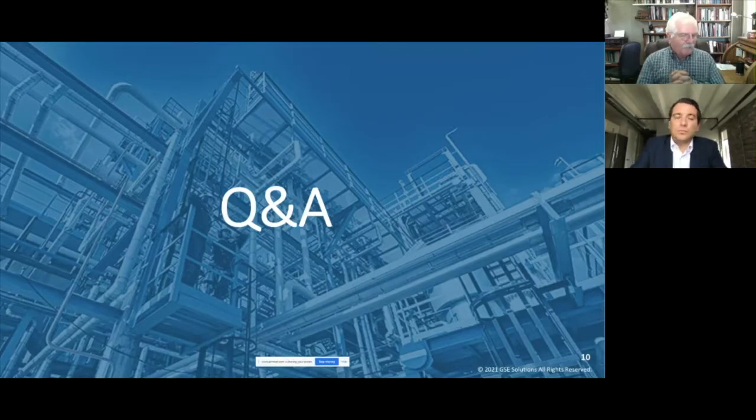And obviously, based on the power recovery discussion that I briefly had, there have been flow errors up to like 5%. We're dealing with a flow error right now at one particular power plant that's on the order of like 9%. So obviously that's a pretty large error. And we identified a pretty significant error at a combined cycle plant of their flow measurement, and it was related to the vendor supplied constituents for the gas, which is obviously used to come up with mass flow, because you need to know ultimately the specific volume. Because of the error of the information supplied for the content of the natural gas, they ended up with like a 5 to 10% error in their flow that we identified with DVR, and they were able to correct.